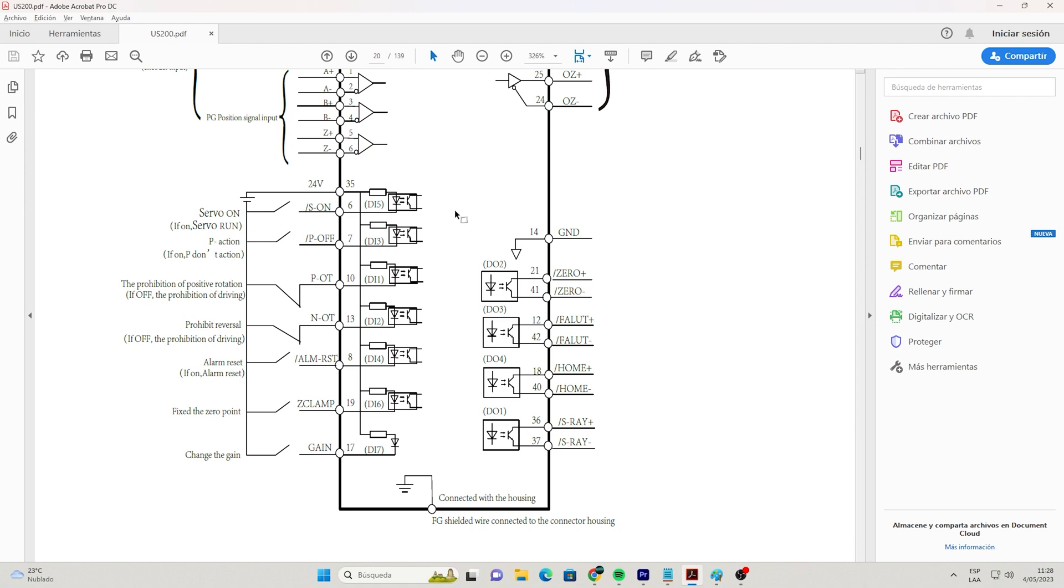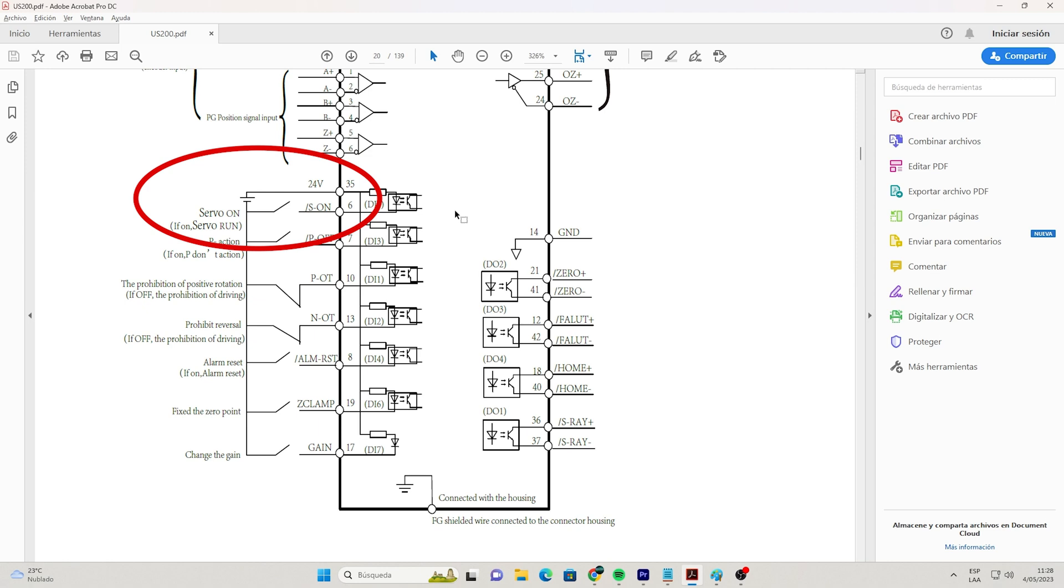We look closely at the power supply. We have that terminal 35 is 24 volt and terminal 6 is the activation in the ON state of the servo drive, which needs a negative to activate. We just need to feed it. Now we look for the servo drive control.